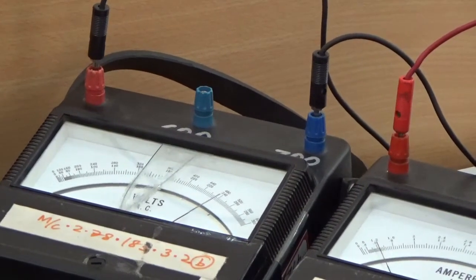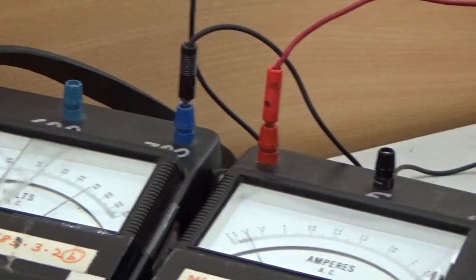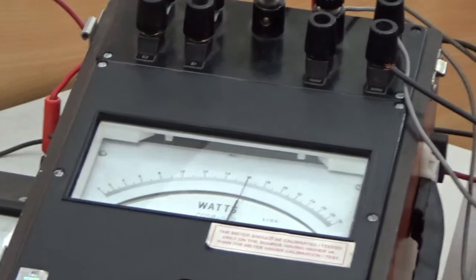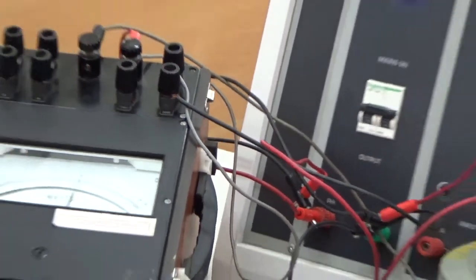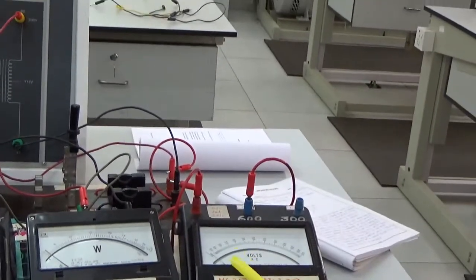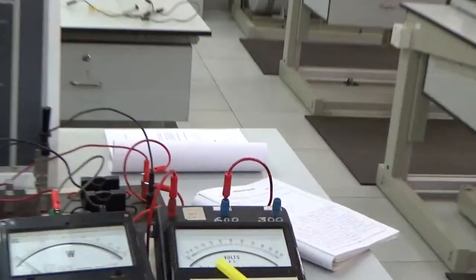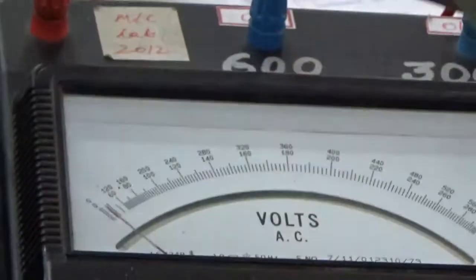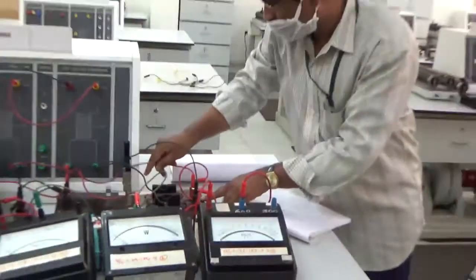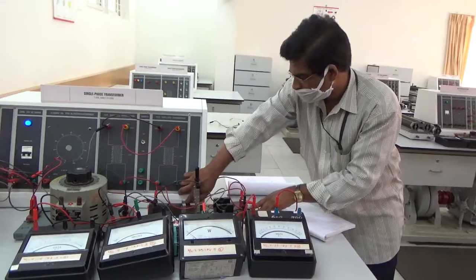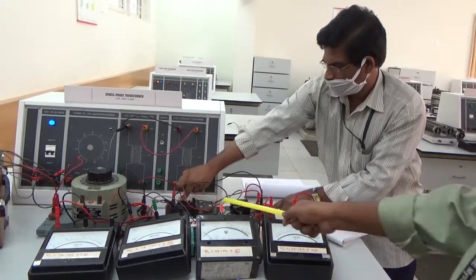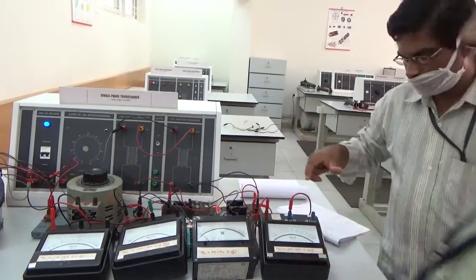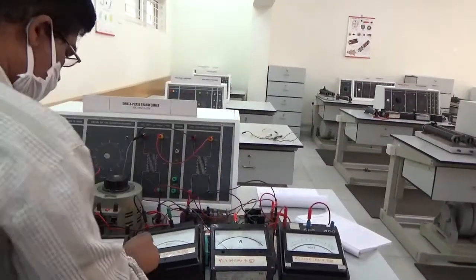Now you can see the readings in the wattmeter. Now I will ensure that the secondary voltages of the two transformers are in phase with each other, so that there will be 0 voltage across this switch. Now the switch is ready for connection to the secondary circuit. You switch on the supply after ensuring it is 0, with the variac kept at the minimum position. I am switching on the secondary side, so the voltage will now be applied across the secondary side of the transformers.